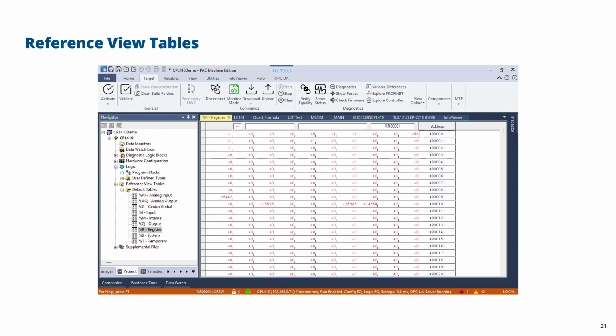You can also change individually for each of these cells what the display format is. Here we're displaying in decimal, so you can see the value for register 1 there. This is the one at the top right, and it's got a value of 50. Moving along to the left, we've got register 1 to 10 on the first line, 11 to 20 on the second line, and so on. These would evolve in real time.